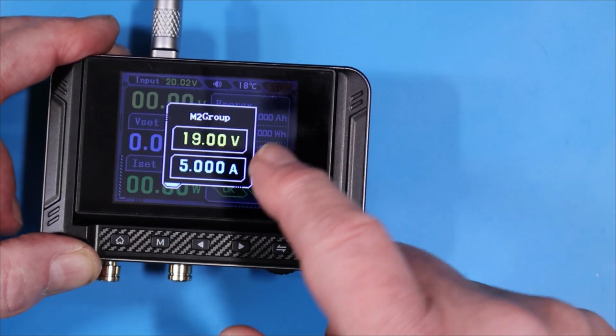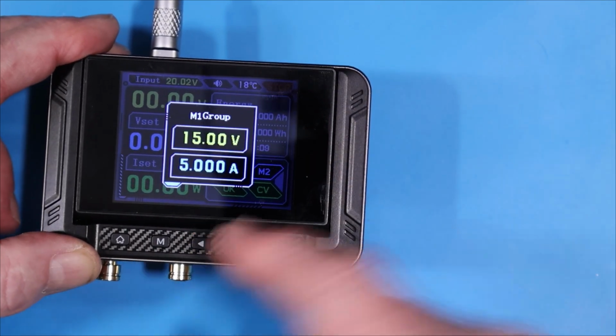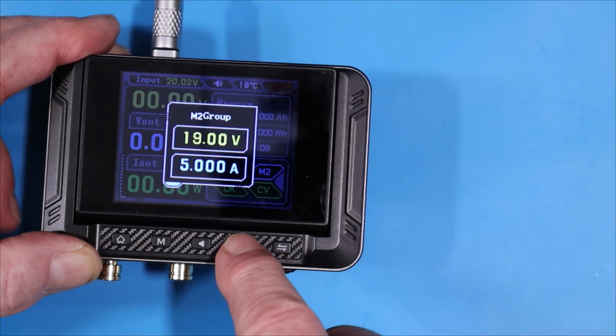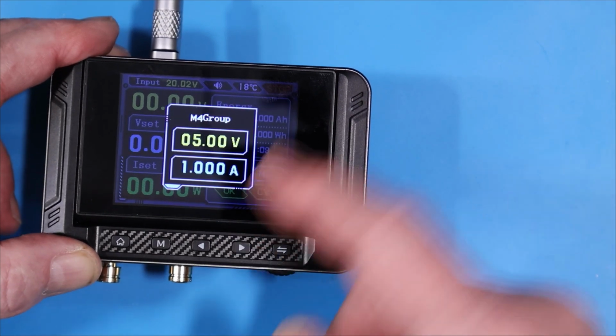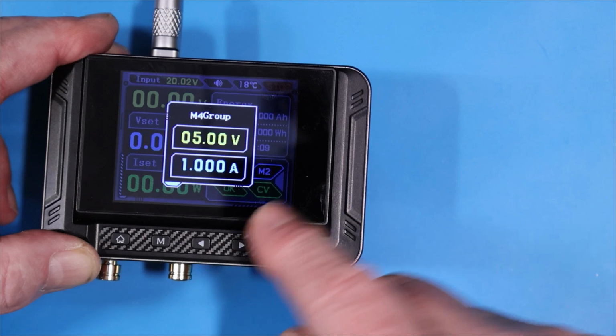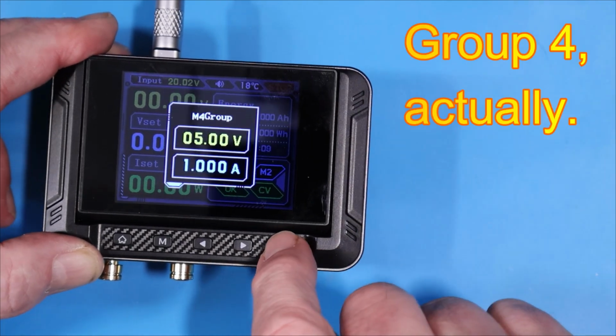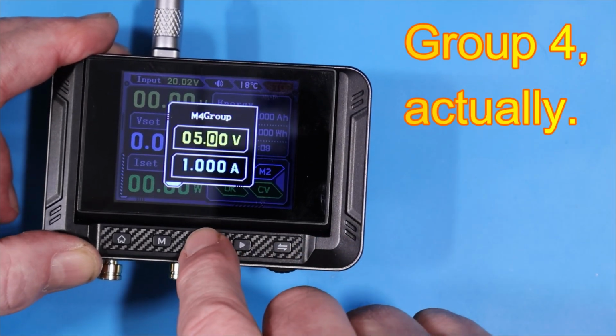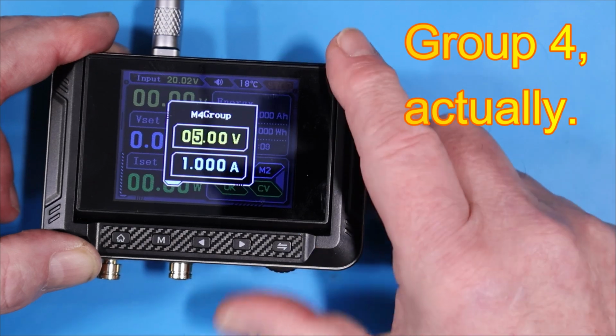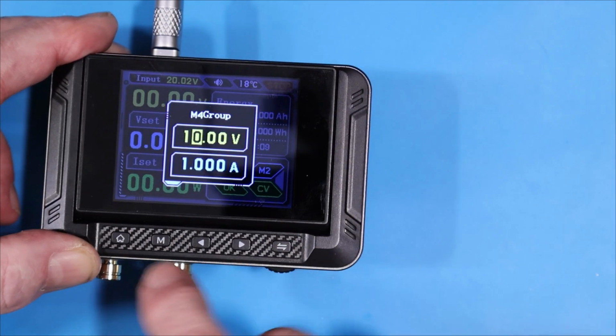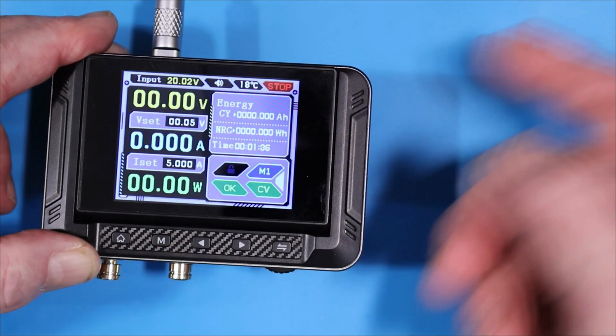That would be handy if it did, because then you could set it without having to go back to that group. But it allows you then to go into whatever group that you want. So these are the memory groups. Here, let's say group 5, if you want to go in there and set that up to something different, you can set it up and make it 10 volts if that's what you want. And press this until you pop out again.